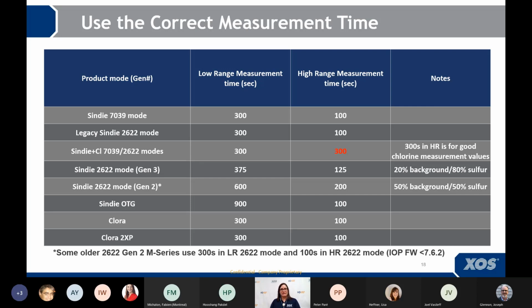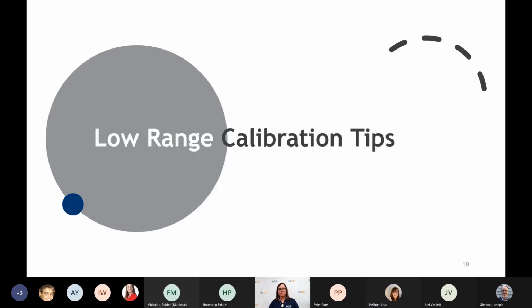But I also want to call your attention here to the Sindie plus chlorine high range. You'll note that I have that listed as 300 seconds in red. Normally, when you're measuring high sulfur, you don't need 300 seconds. That 300 seconds isn't for the benefit of the high range sulfur measurement. It's because while you're probably measuring high range sulfur, you're probably measuring low range chlorine. And so you need that 300 seconds to get a good chlorine measurement, provided that you have a stable chlorine sample. So that's why we have the default measurement time set at 300 seconds on the Sindie plus chlorine analyzer. Let's move on to low range calibration.